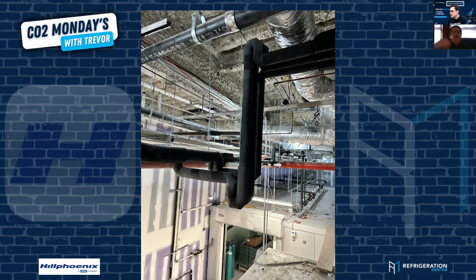We come off the side of our CO2 lines. The reason we do that, because we discovered way back before I even started here, that if you start to get low on CO2 and you come off of the bottom of the line, the first 2 circuits will eat everything. So we come off the side, and that way we stand a better chance of everybody getting a little bit of liquid to keep the systems cool.